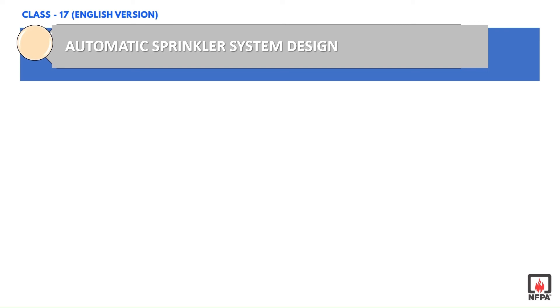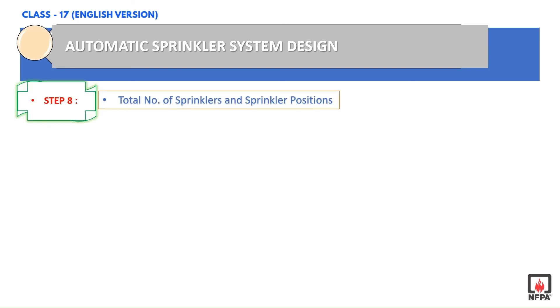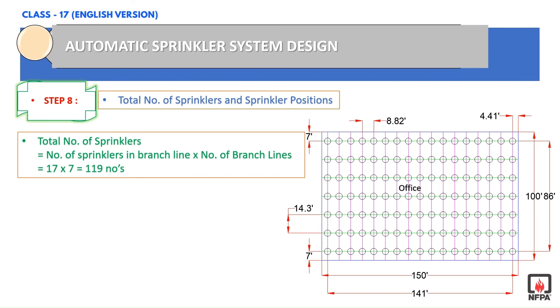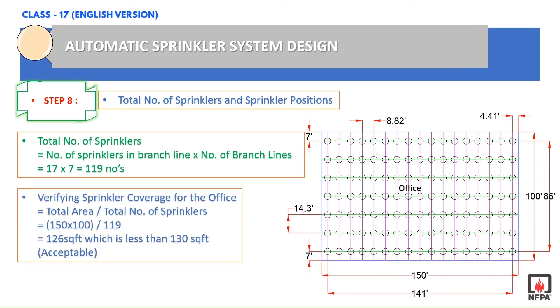Step 8: We calculate the total number of sprinklers and position them. Using the formula shown on screen, we get 119 sprinklers for the whole office area. The sprinklers are placed on the intersection points of the branch lines. We verify the sprinkler coverage by dividing the total area by the number of sprinklers, getting approximately 126 square feet per sprinkler, which is acceptable since it is less than 130 square feet. So our design is acceptable.